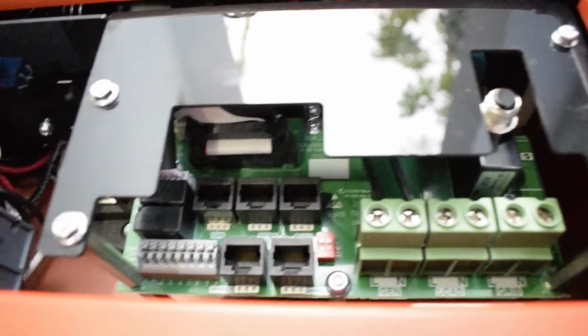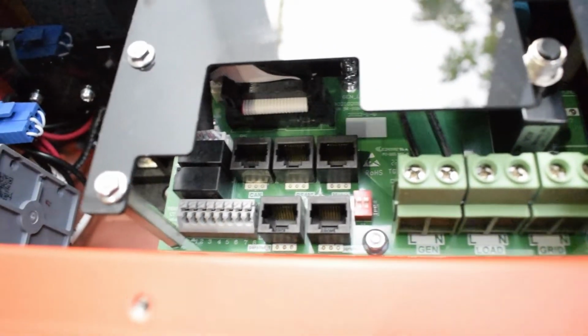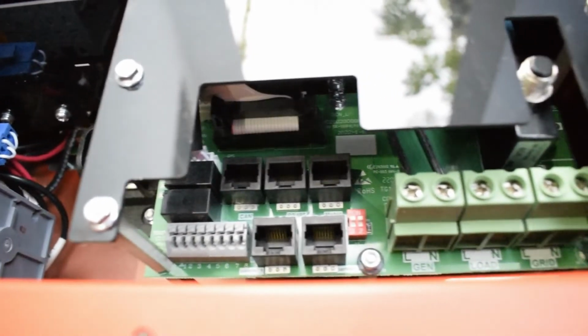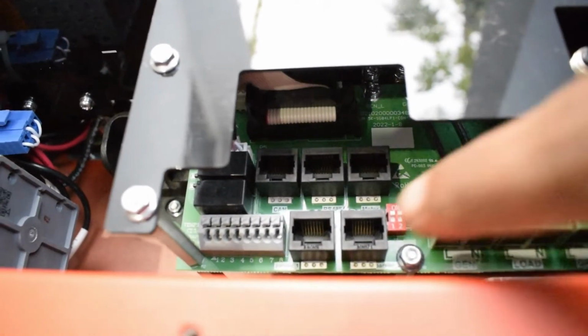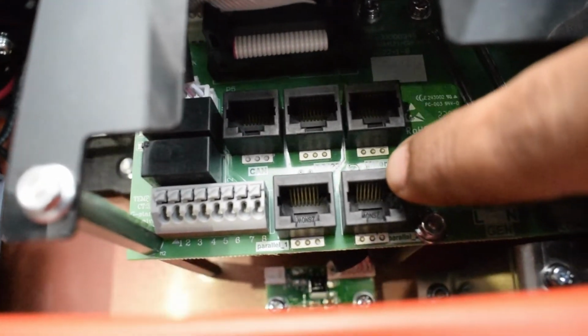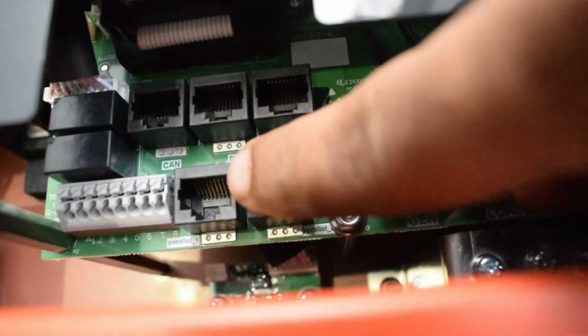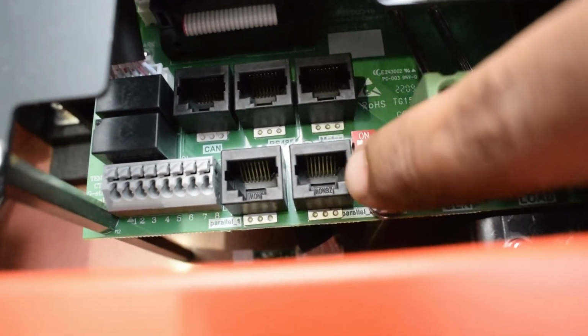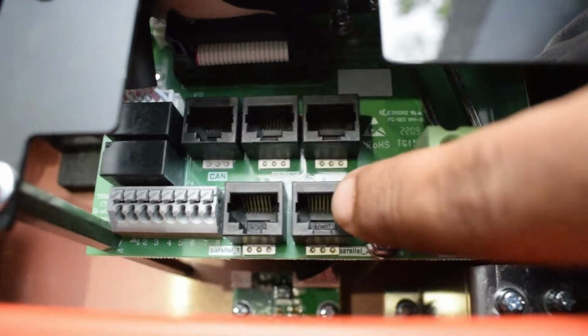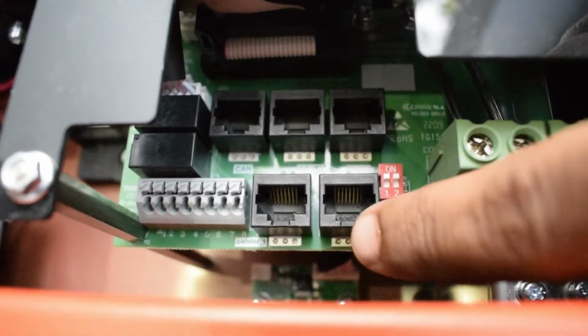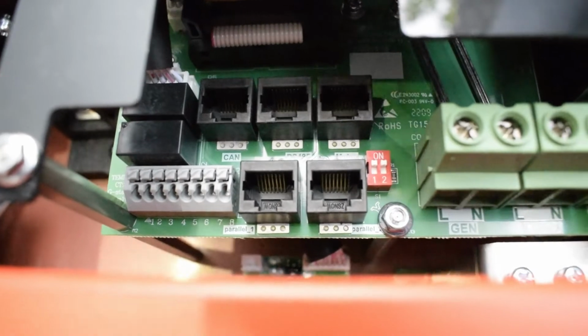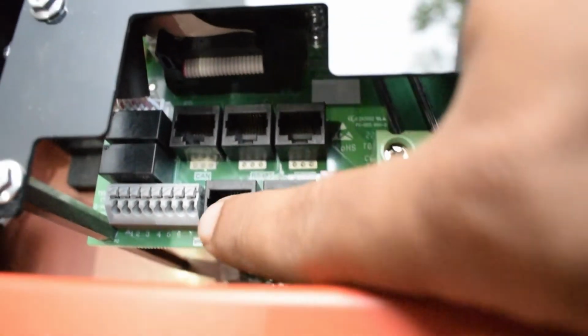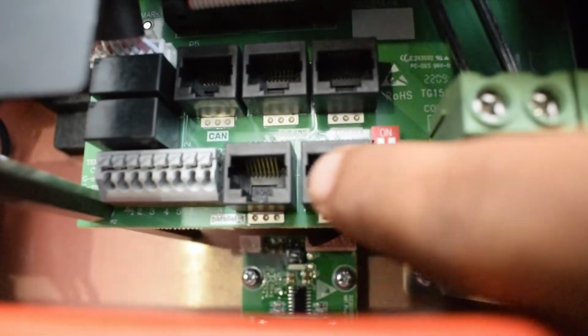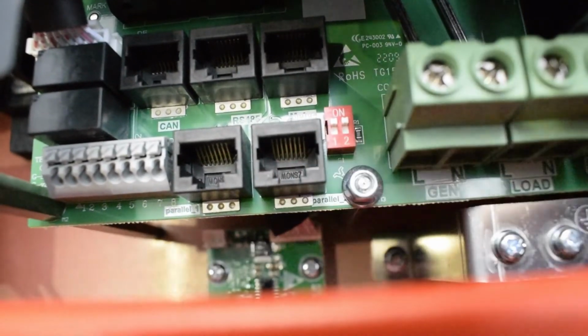We need to connect 4 batteries of 12 volt and make a parallel, or we connect a 48 volt lithium based battery bank. Okay, again, this is the function port and this is the parallel port. If we need to connect 2 or 3 inverters, these ports need to connect with the inverters. For the second inverter, the Cat5 connection cable will connect with this and another inverter, and for the middle inverter, both the first inverter port comes into this point and the second inverter port goes to the third inverter.